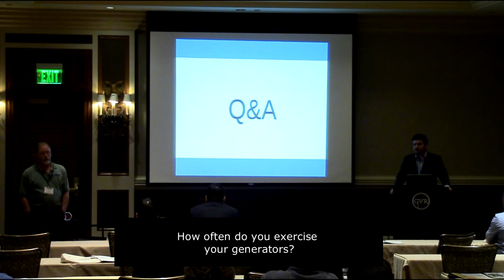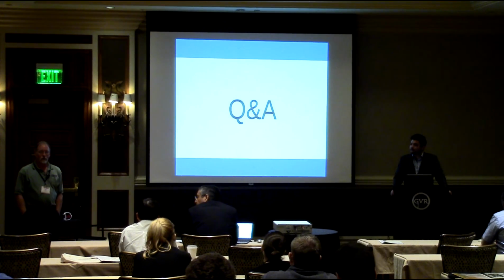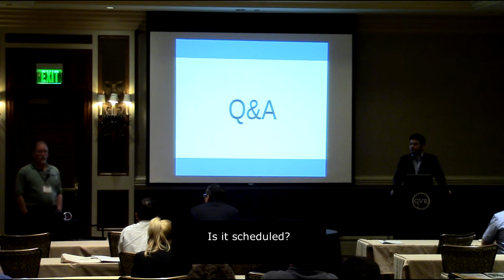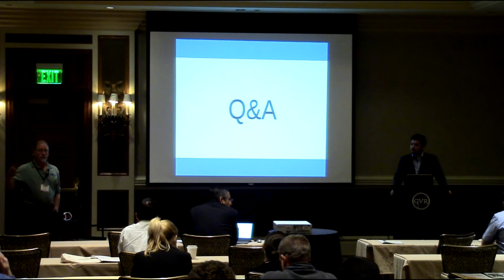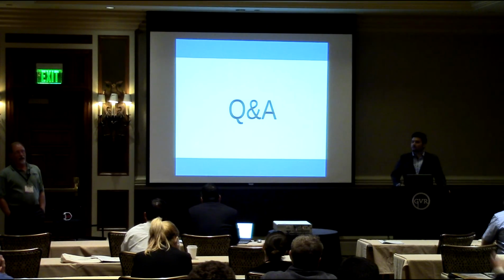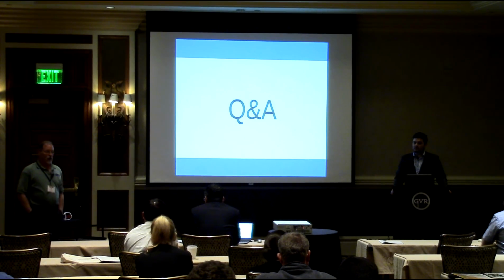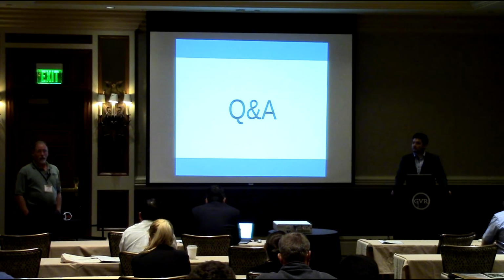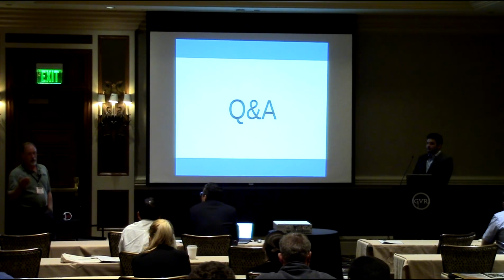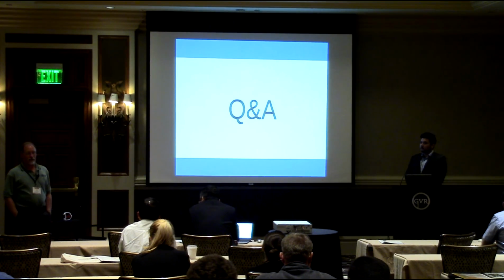We exercise our generators once a week. What's that? Is it on a schedule? Yeah, it's scheduled. We have it automatically set. It's every Tuesday at 10 o'clock on one generator, and Monday at 9 o'clock on our warehouse crew generator. They exercise, make sure that they're up. And what's nice is we've caught problems because of that. They'll exercise, they won't fire up for some reason, and we can get the generator mechanic in and find out what the deal is. It's saved us quite a few times.